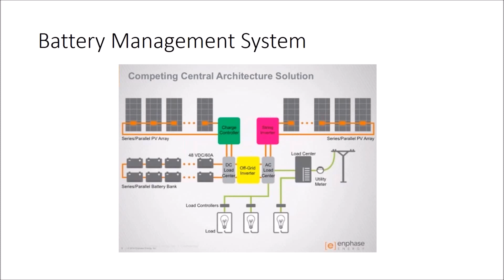You want that communication, that digital communication. You don't necessarily need it between the inverter and all the other renewables on site, but you want it between the batteries. You can't have two master battery inverters. You need to have one master driving the whole system. So you could have 3, 4, 5, 6 different battery inverters on the same site. They all have to be the same brand.